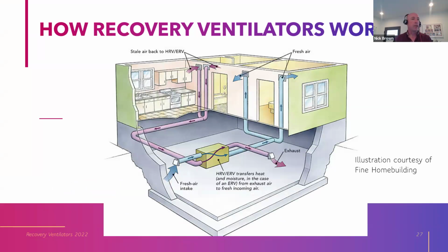I like this cutaway diagram from Fine Homebuilding that allowed me to use it. So you see the fresh air intake, that's the blue duct. It looks like here it's coming from an exterior wall, perhaps in a basement. The fan in the unit is bringing in that fresh outside air, hopefully running it through a MERV 13 filter in the box. And then that air continues in the blue ducts as supply throughout the house. You're showing one in the bedroom, one in the living room in this simplified cutaway.